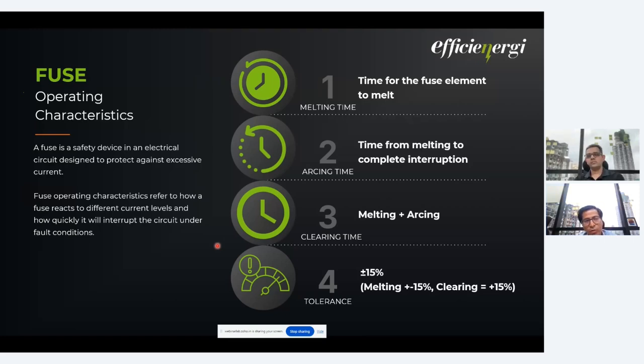So there we use fuses. Again, that is a topic we'll be covering in the other webinars, where we will be talking about selectivity and protection. So here we are talking about the operating characteristics of the fuses. It basically comprises two times: one is melting time, and the second is arcing time. Both of these together make up the total clearing time, which is what we call the complete operating time of the protection device. So here it is a fuse.